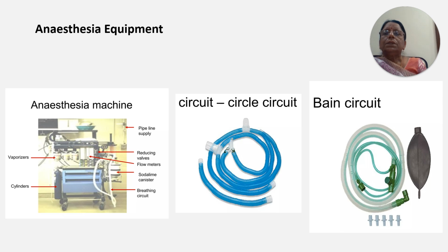So this is the anesthesia equipment. The anesthesia machine is very important for performing these procedures. So you have to check each and everything, whether it is in working condition or not. Whether the oxygen backup facility is available or not, and all vaporizers for inhalational anesthesia, the soda lime canister, and breathing circuits, everything is in working condition or not. You have to keep it ready.